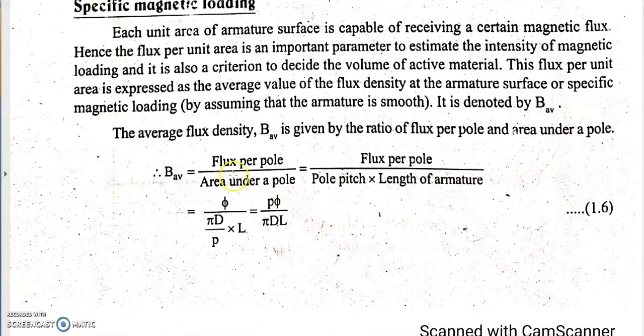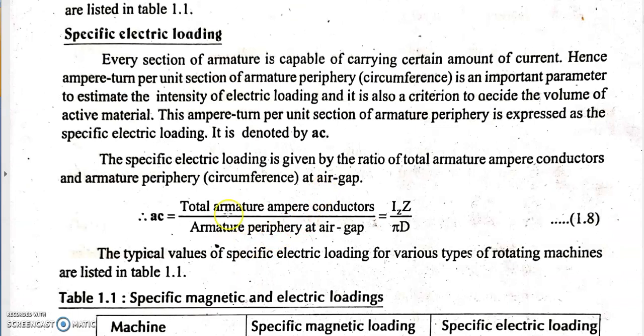Two more terms are specific magnetic loading and specific electric loading. Specific magnetic loading B_average is flux per pole divided by area under a pole. The flux per pole is φ, and the area under a pole is the pole pitch multiplied by the armature length L, where pole pitch = πD/P. So B_average = Pφ / (πDL). Specific electric loading AC is total armature ampere-conductors divided by armature periphery at the air gap. The total armature ampere-conductors is Iz × Z and the armature periphery is πD.